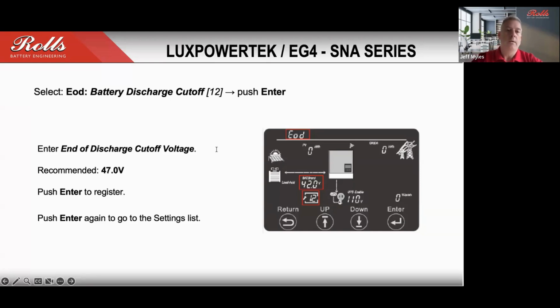One thing to note, with most LFP products, the battery management system, the BMS, is essentially controlling charge and discharge to the battery, but it's also managing balance and so on. And the more that BMS has to work to try to correct for conditions that are not optimal, then it's more likely to wear down the BMS and potentially run into a situation where the BMS needs to be repaired or replaced.